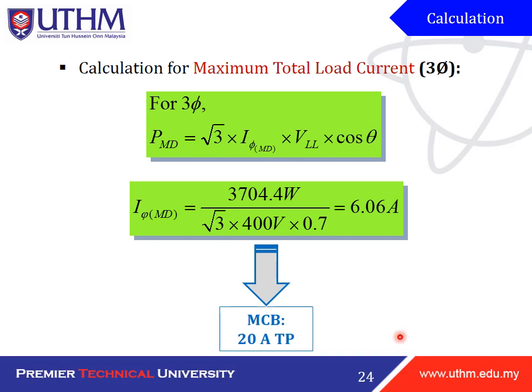And then from the power maximum demand, we can also calculate the maximum total load current for three phase. So we have this equation, so rearrange the equation, we get it like this and calculate it, and we have 6.06 ampere, which can be used in the MCB 20A three-pole.